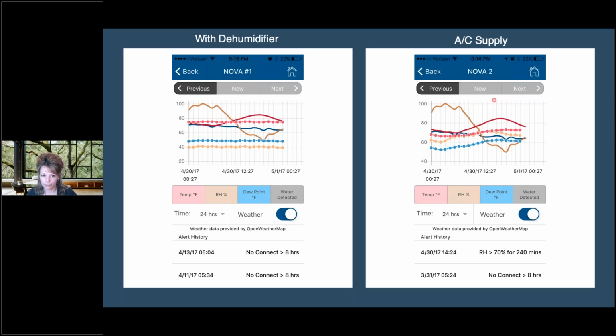But you can see we kept it at 40%, even though the solid orange line, which is the RH outside, was up to 100%. We had rain going on some days. But on the right side, the AC supply was utilized in the other crawl space, and that dotted orange line was consistently above 60%. I was getting alerts because we were monitoring it; it was consistently hitting 70% during that time frame. So it does not control the RH in those spaces. And again, we're talking April, not a lot of AC being run in Northern Virginia at those times.